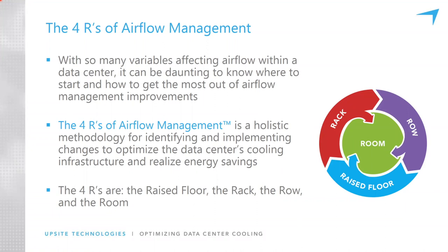We might get rid of some hotspots by addressing airflow management at the rack, row, and raised floor level, but it's when you make adjustments at the room level that you really see the benefits. And we'll talk about that more in just a moment. Also, the raised floor and the rack level airflow management are really prerequisites for getting the most out of containment. So I've been in a few sites that have containment, but they have perforated tiles in the wrong locations, or they have cabinets that have no blanking panels in them. And that was really kind of some money wasted to not address those issues at the raised floor and the rack level first. And if maybe you haven't done that, you do have some containment in place, it would be good to go back and address those, look at that.